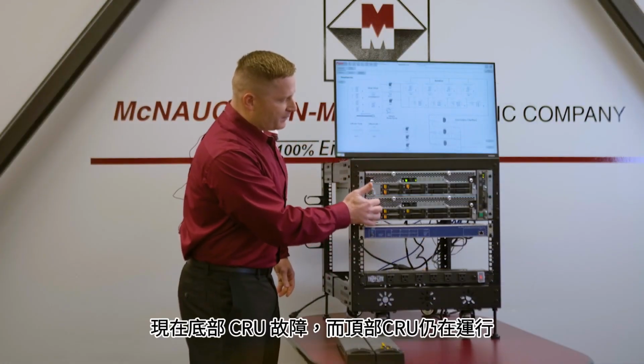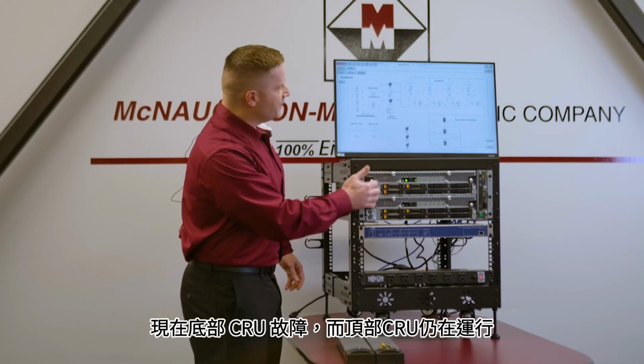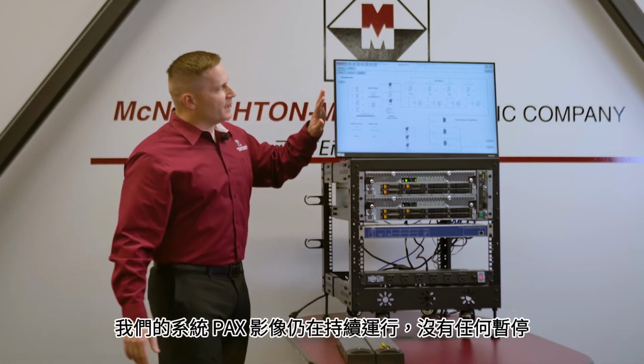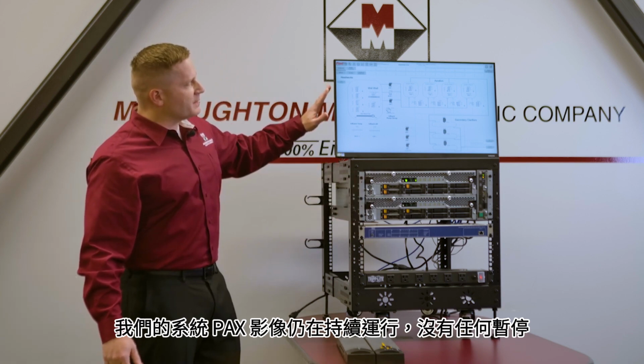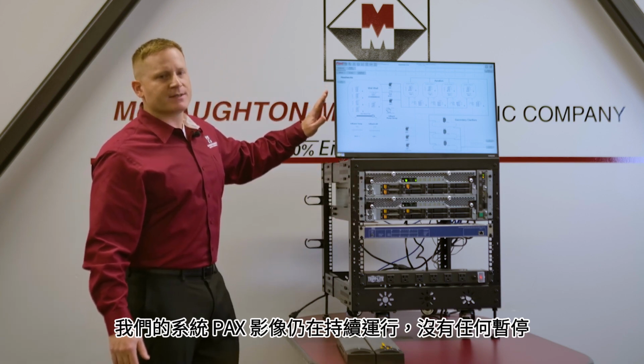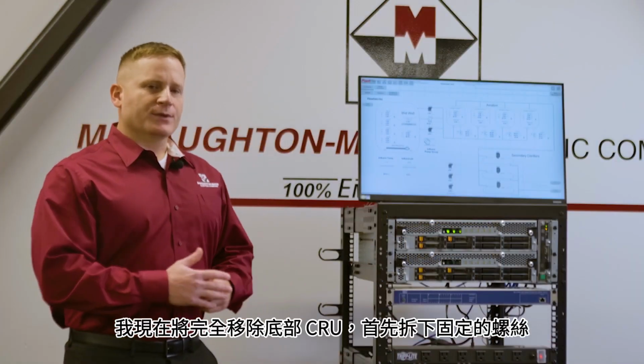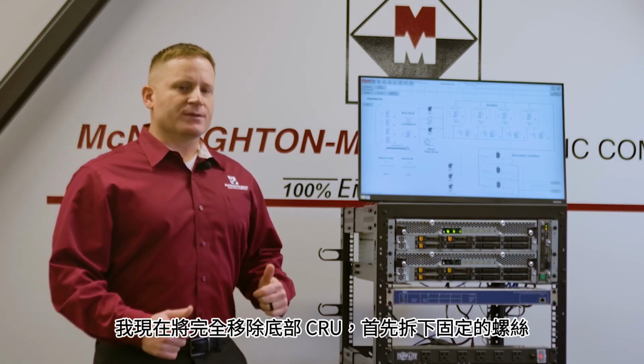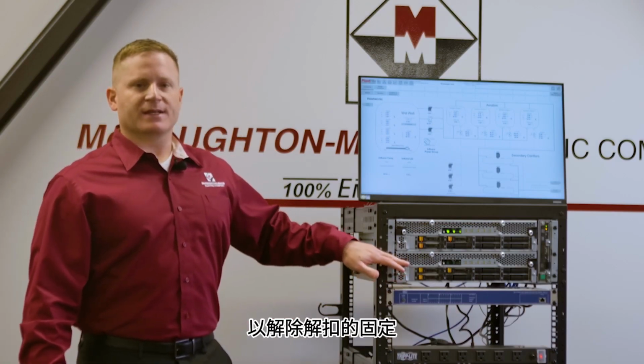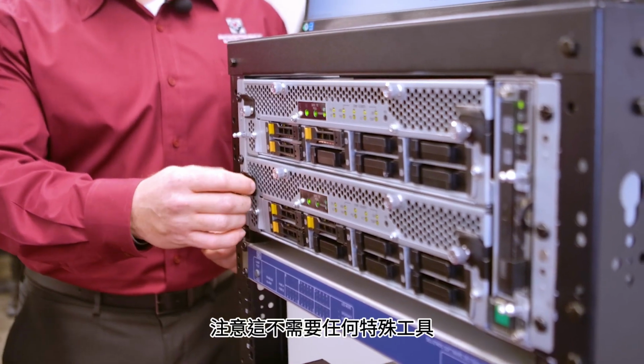So now we have a bottom CRU failure and the top CRU is still in operation, and our PlantPAX image is still running without any pause. I will now remove the bottom CRU completely by first removing the screws securing the locking latches in place. Notice this requires no special tools.